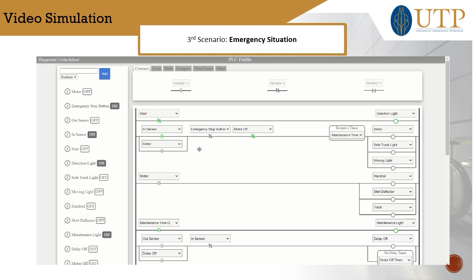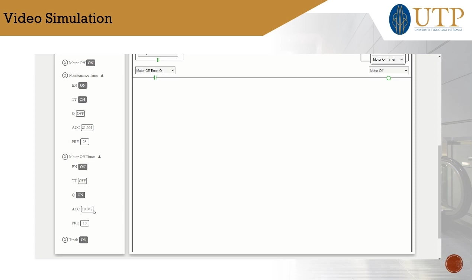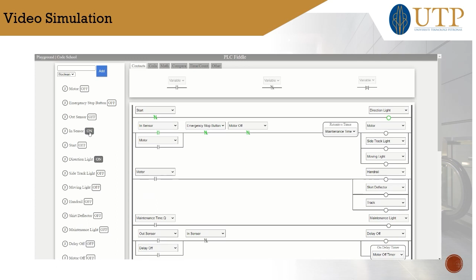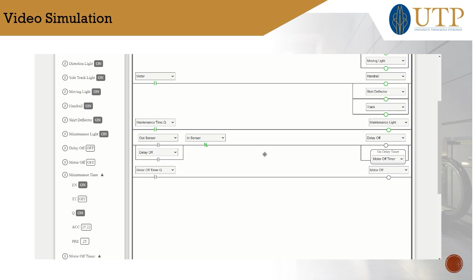Alright, so for the maintenance time timer, we use a retentive timer. Let's simulate it. Once the motor is on, you can see the maintenance time timer starts running. So let's say we turn on the out sensor and it reaches 10 seconds. Let's wait for a little bit. Alright, you can see the motor is off and the timer here stops running. This indicates that the maintenance time accumulates to the total operating time of the escalator. So we turn on the motor again, and when it reaches 25, the maintenance light is on. So the function works well.